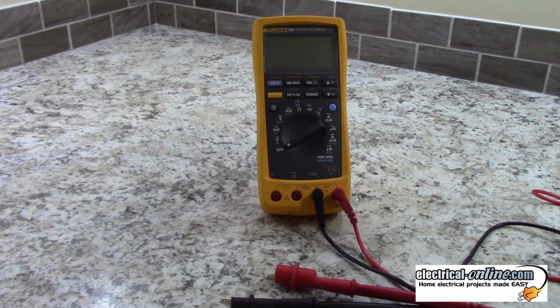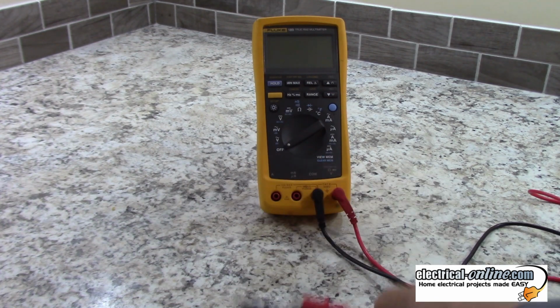So there's a couple ways you could do that, but without power or voltage on the circuit, the best way would be to take the positive or the black wire at one end and just connect it temporarily to your ground wire, and then go back to the other end where you're trying to find out if it's the same cable, and you measure for resistance between black and ground.